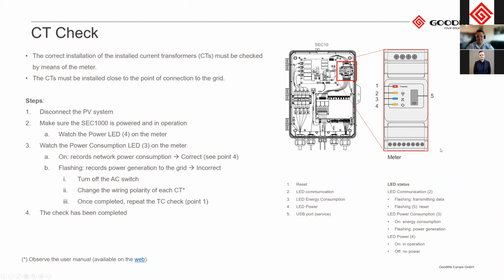For the CT check, which I did mention previously, we can also check it in this manner. So if we're on site, we can look at the meter. Inside the SEC, this is a GoodWe smart meter. That is our standard three-phase meter, our GM3000. This meter is hot swappable. Should anything happen to the smart meter, it is the exact same meter as our normal GM3000 meter, except we have the special conversion board for the normal 5 amp ratio CTs.